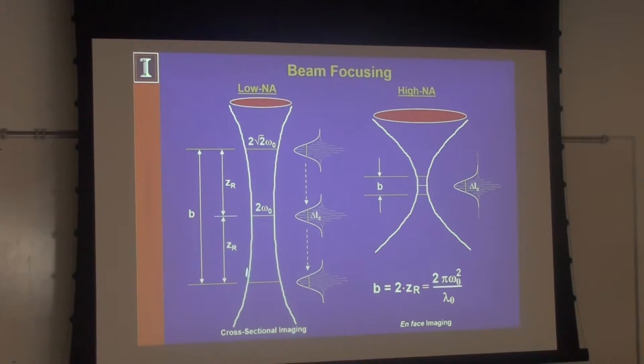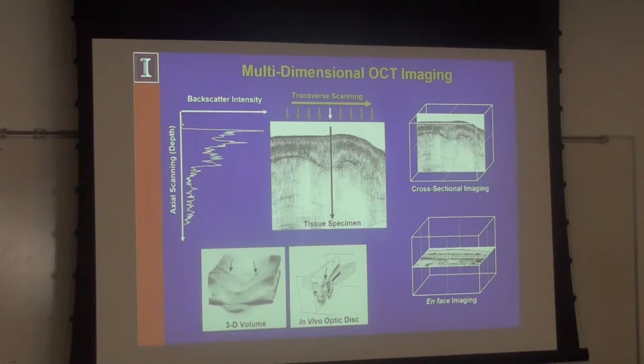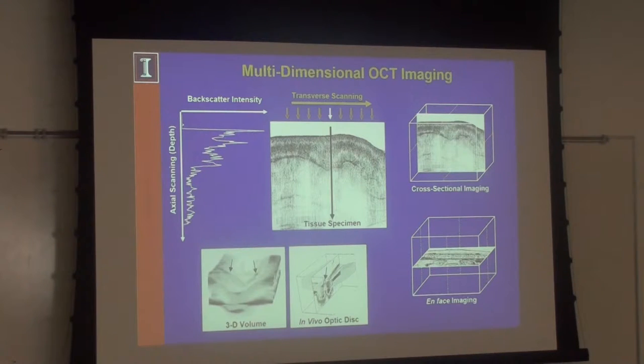For low NA systems, cross-sectional imaging in depth is preferred; for high NA systems — optical coherence microscopy — you do en-face imaging like a standard microscope. To do OCT we acquire single depth scans or A-scans, and the envelope shows attenuation in tissue because of scattering and absorption. That represents a single column of data where the intensity represents the degree of optical scattering coming back from the tissue. We step our beam over, repeat the measurement, and assemble two or three dimensional images based on label-free, endogenous optical scattering properties of the tissue.